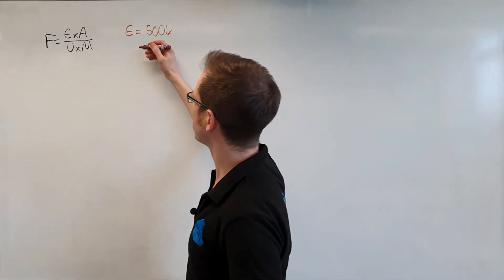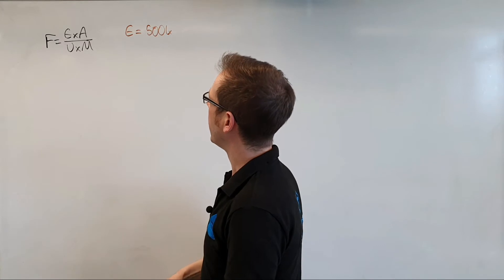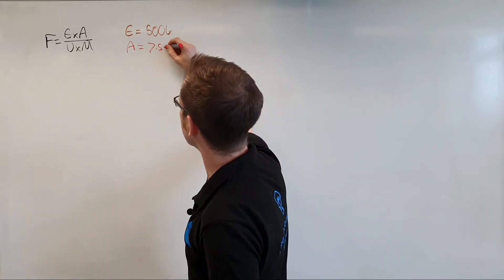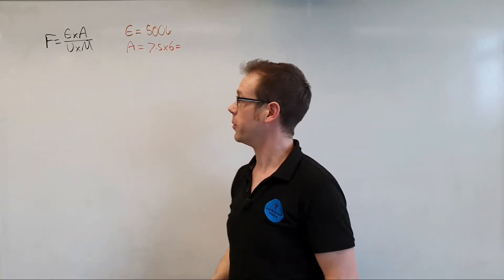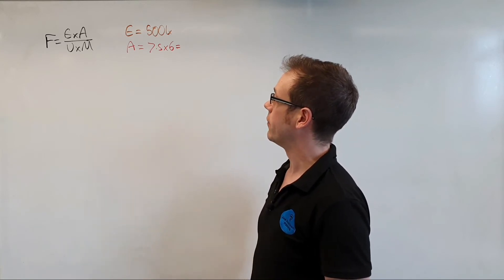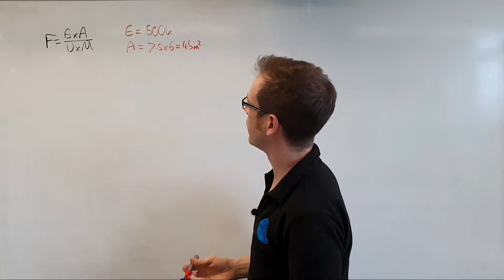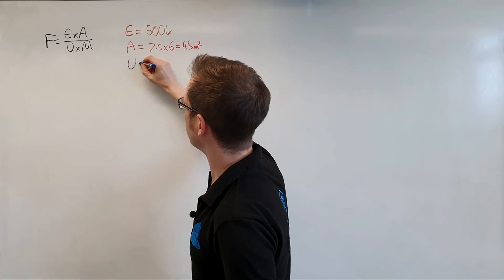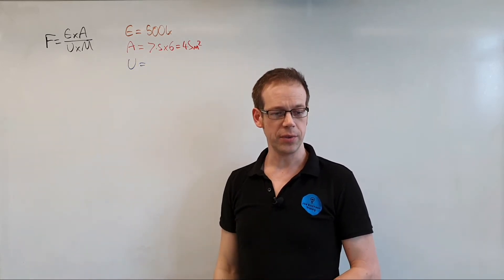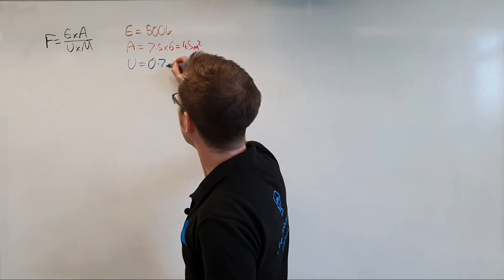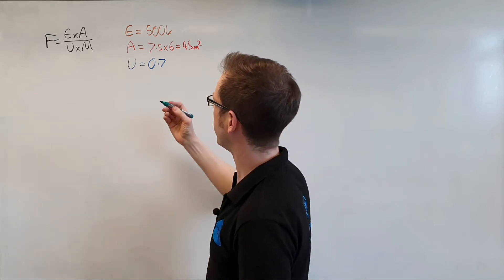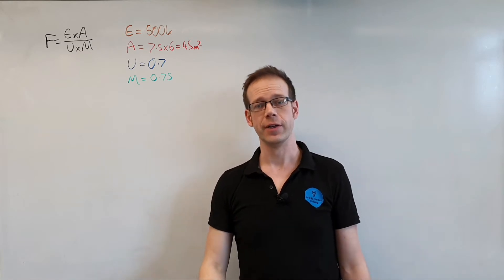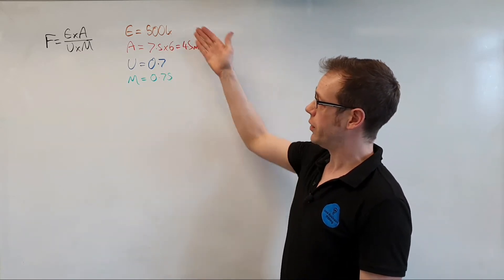We then need to figure out the area A, which we calculate by multiplying length by width: 7.5 times 6 gives us 45 square meters. The question also states the utilization factor U is equal to 0.7, and the maintenance factor M — which has no units — is 0.75. So we've got all the numbers we need lined up straight away.